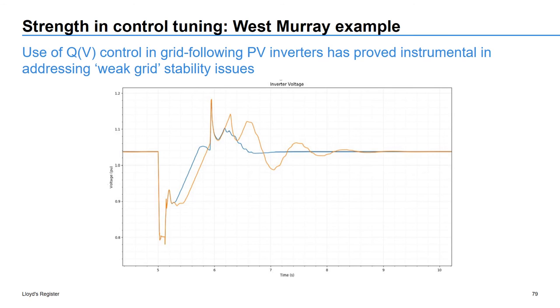If we look at the orange trace in this diagram, we had a response to a large disturbance that was relatively underdamped. And by retuning the slope parameter of that QV control, we achieved the response in the blue trace, which was substantially more damped. So in this case, an issue that did arise from a weak grid and from a relatively low system strength environment, which in this case just meant a higher sensitivity of local voltage to power flow, was managed through control system tuning.